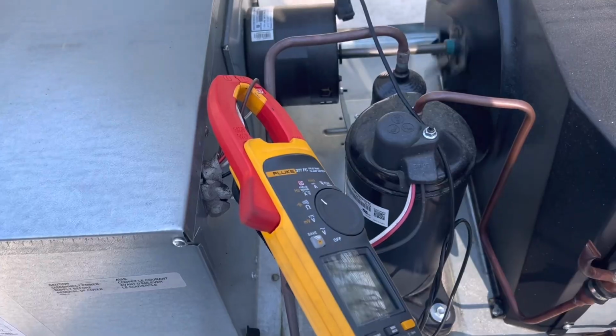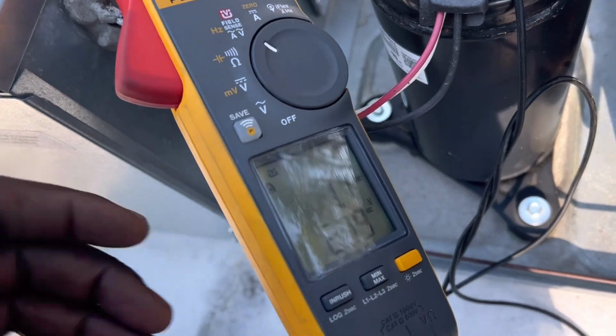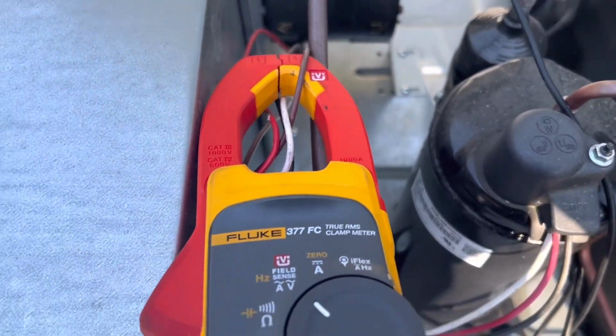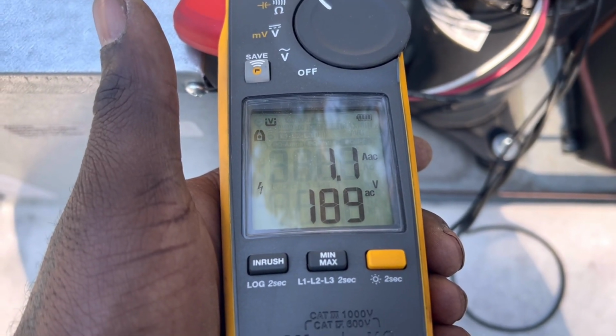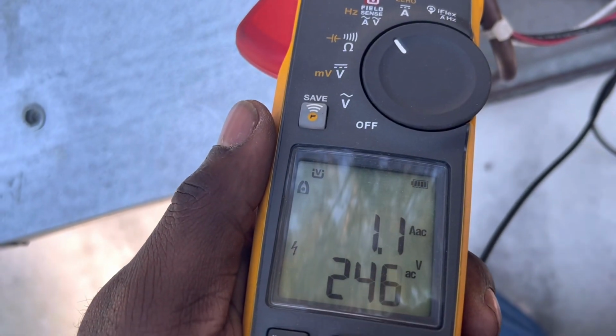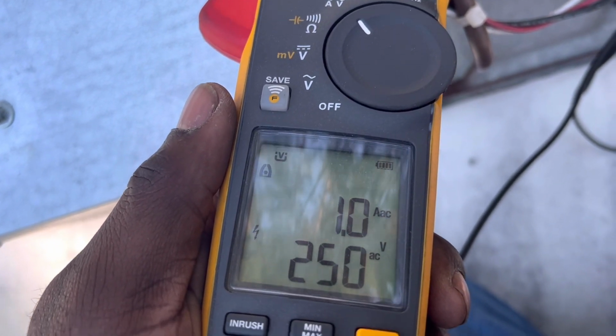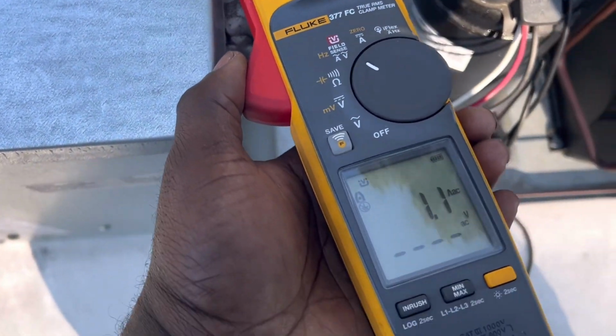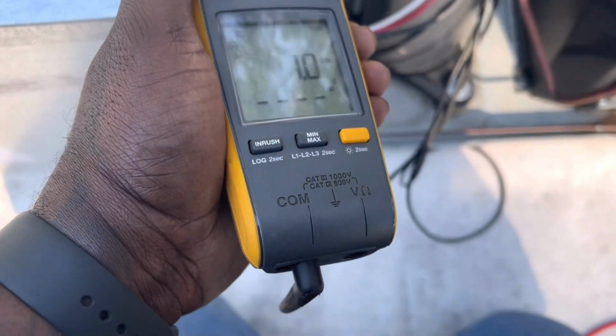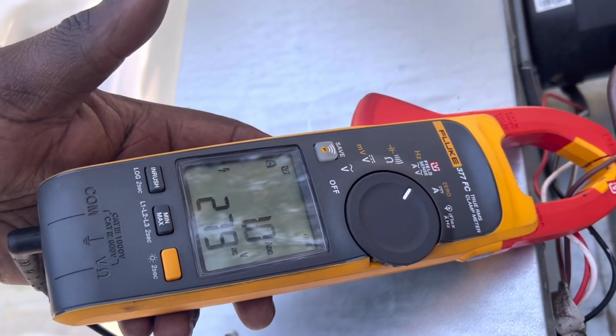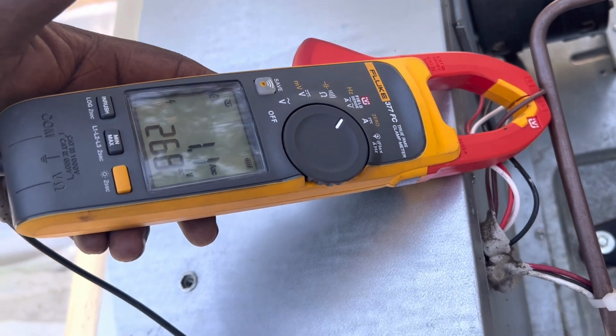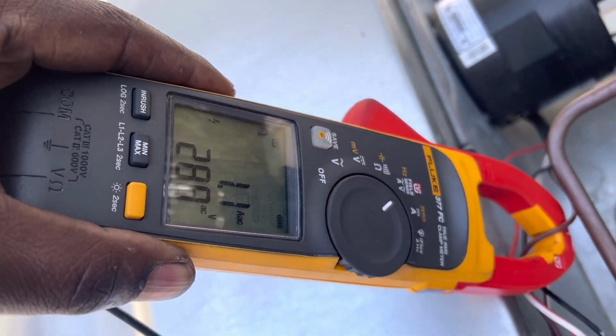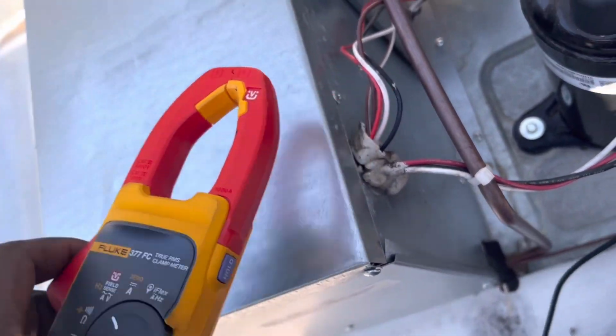It's going to be the brown wire. So as you can see with the field sense, we got a good brown. On the brown wire, it's saying it has 187 volts fluctuating around AC. So I'm reading the voltage through the amp clamp. Not very stable. You kind of have to have it just right, away from the other wires, or it affects it. But this fan's pulling about 3 amps.